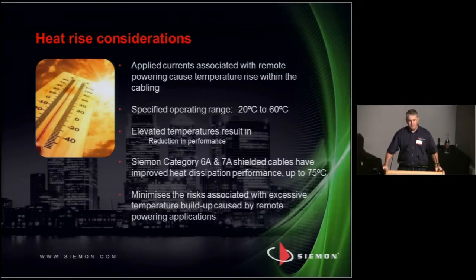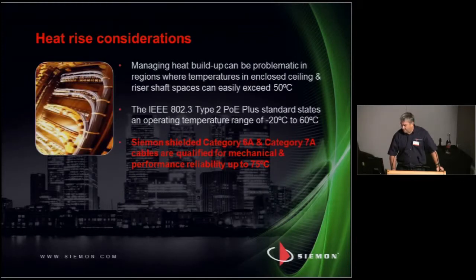So the infrastructure will reduce in its length because you have attenuation, and that's above 20 degrees C. Getting to 40 degrees C, unshielded cables actually fall off quite a big cliff. I'll show you some graphs in a minute, and you'll see how much distance we lose. So now we're going to put power down it. I say PoE plus showed a 10-degree increase, so now we're up at 30 degrees. Go into some of the areas where they're behind the glass and everything else, and the temperature's creeping up dangerously close to our maximums.